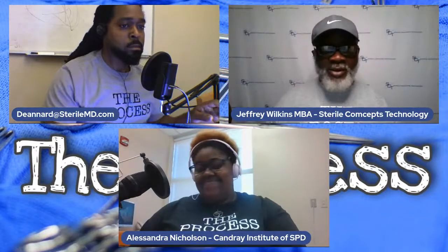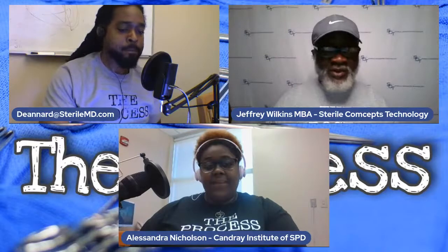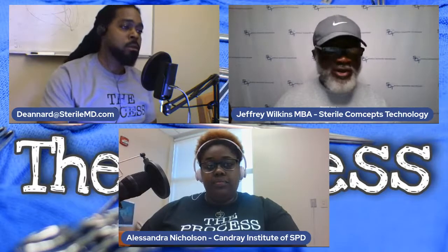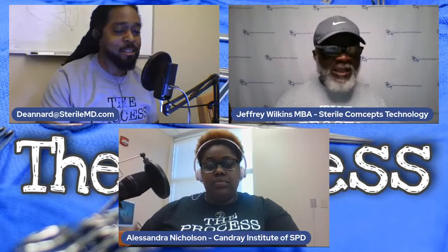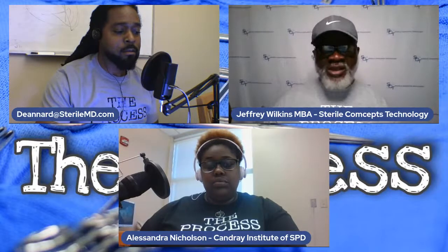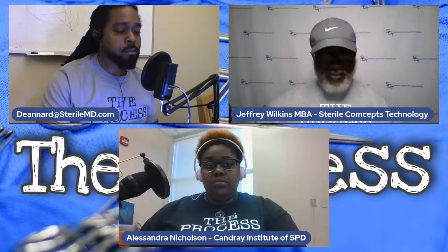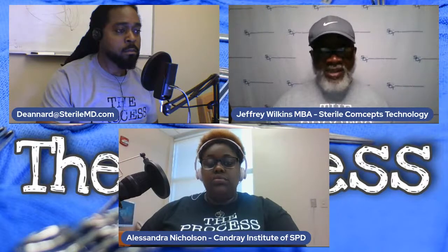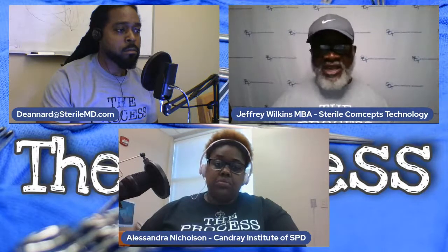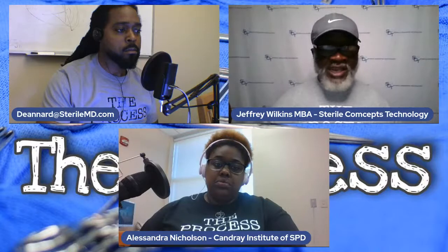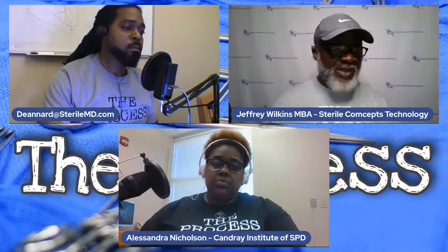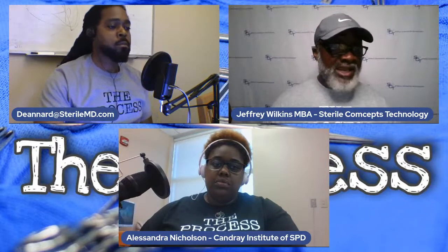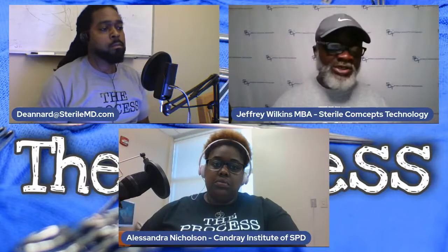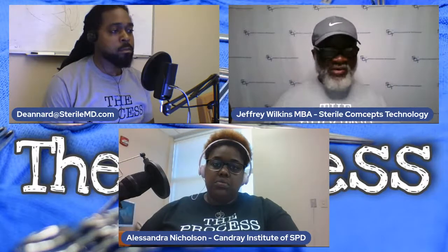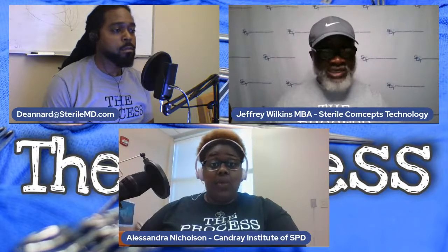So IFUs are extremely important. Understand them, research them, review them. Denard, you're the computer whiz. Say, for example, with OneSource, do they have a setup where, if the IFU is out of compliance, they will tell us, "Hey, listen, this IFU is not current"? Because what happens is I look on OneSource and may see an IFU from 5 years ago, and I just had an in-service with the rep, and he said these are the newest, latest, and greatest. Where's the IFU to show that that's validated for the same process he's presenting?